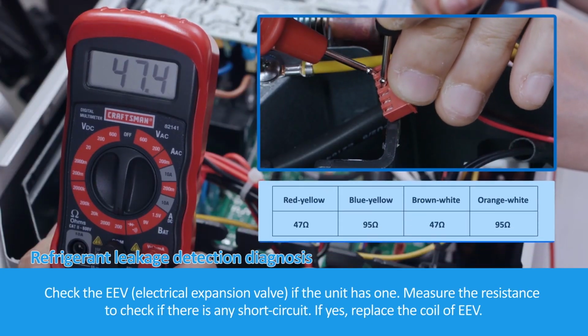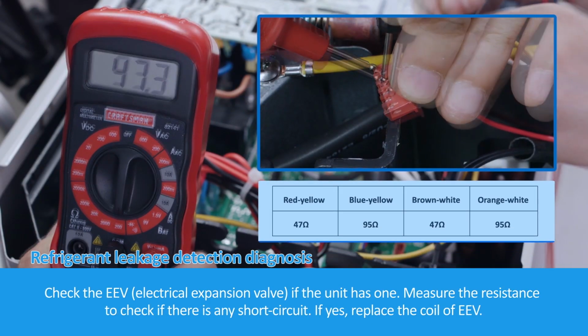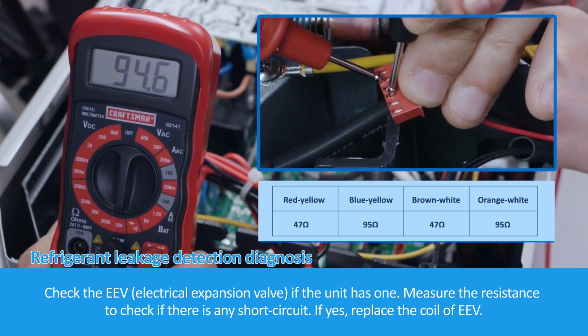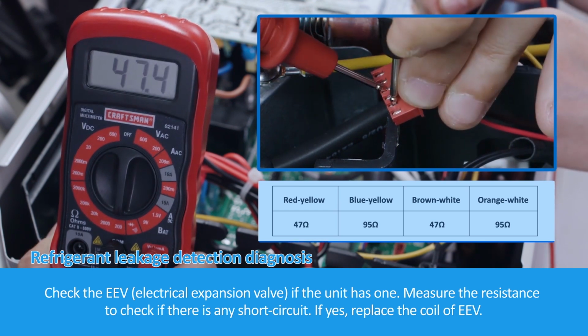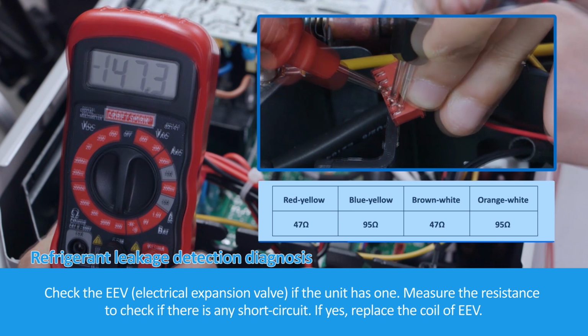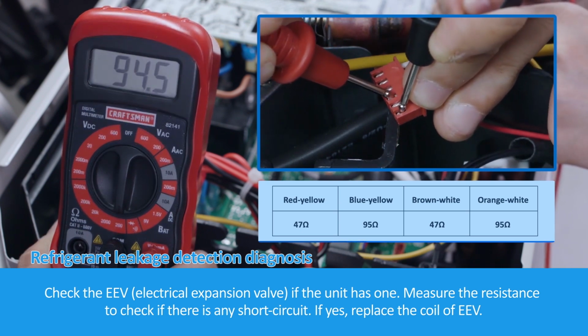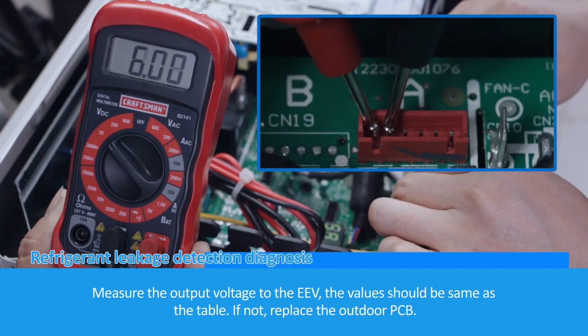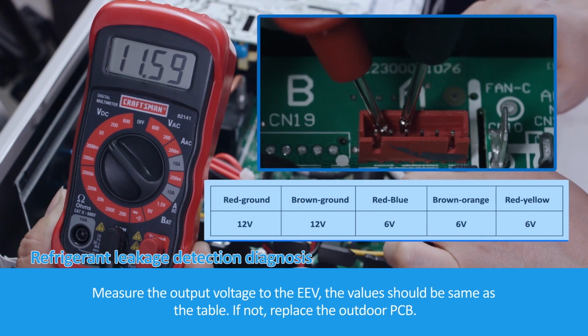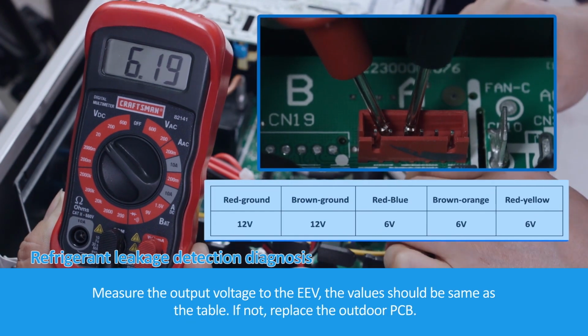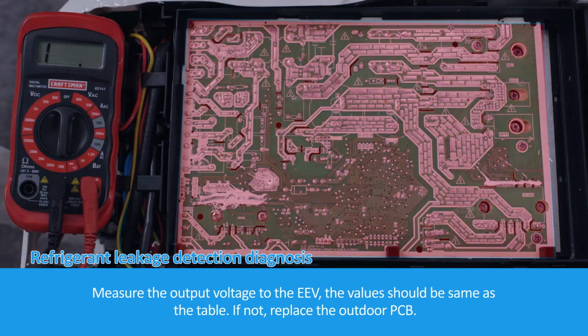Check the EEV electrical expansion valve if the unit has one. Measure the resistance to check if there is any short circuit. If yes, replace the coil of EEV. Measure the output voltage to the EEV. The values should be same as the table. If not, replace the outdoor PCB.